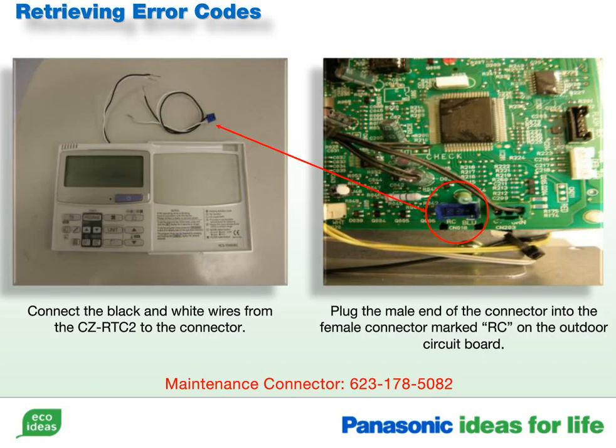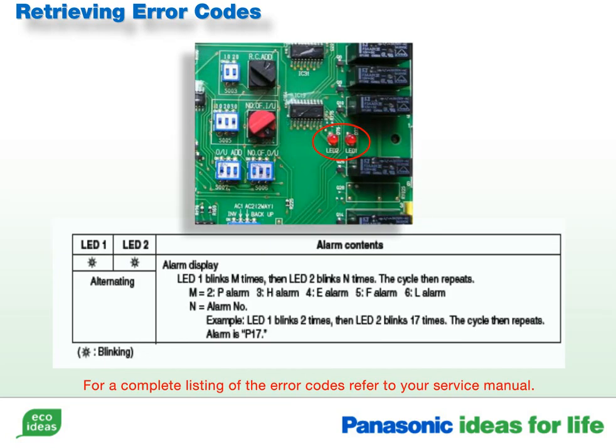Connect the wiring harness to the CZ-RTC2, and plug the harness into the female connector labeled RC, on the main board. How to read alarm codes using LED 1 and 2. If the unit has a P17 error code, LED 1 would blink 2 times, this means that the letter code of the error is a P, and LED 2 blinks 17 times, so we now know we have a P17 error code present.